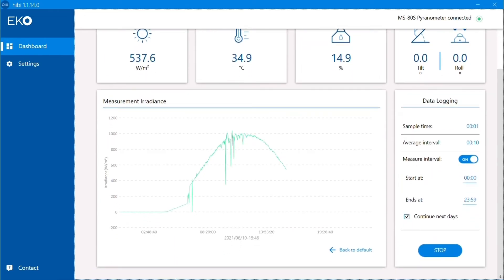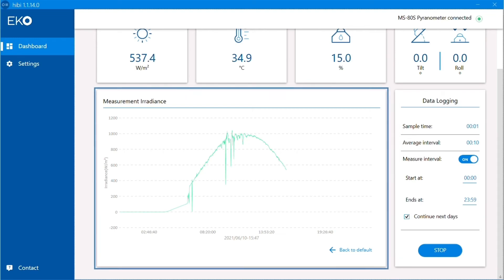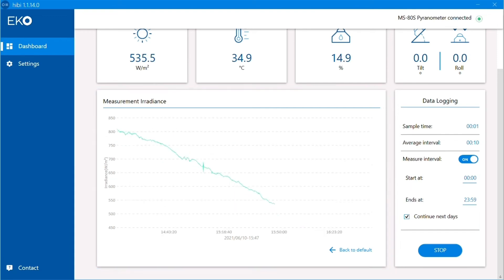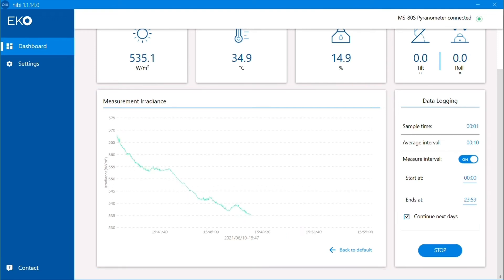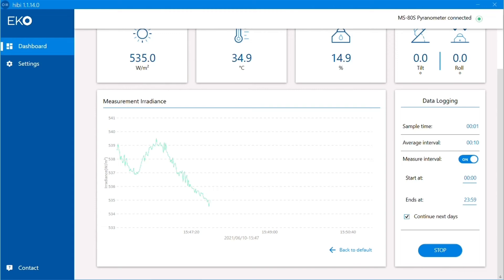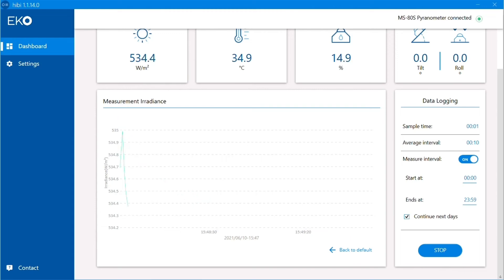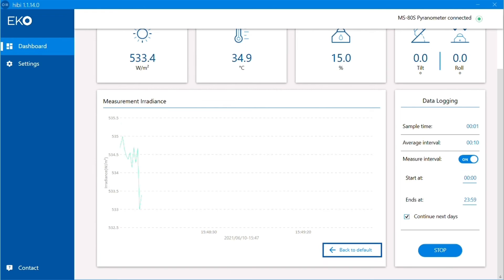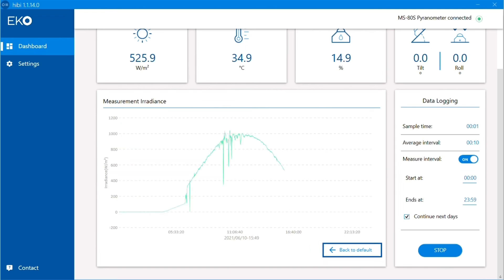Just below that, you can see a live graph of the measured irradiance data, updating every second. This graph is interactive, so you can scroll to zoom in and out, drag to move through the time axis, and if we scroll all the way in, we can even see the irradiance data being measured in real time. Of course, we can always back out by clicking Back to Default.